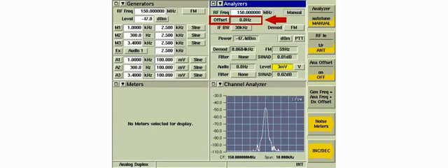Frequency accuracy is measured with either the offset meter or the counter. The DMOD button selects the demodulation format. The DMOD can be set to AM, FM, upper sideband, or lower sideband. FM de-emphasis is also selected here.